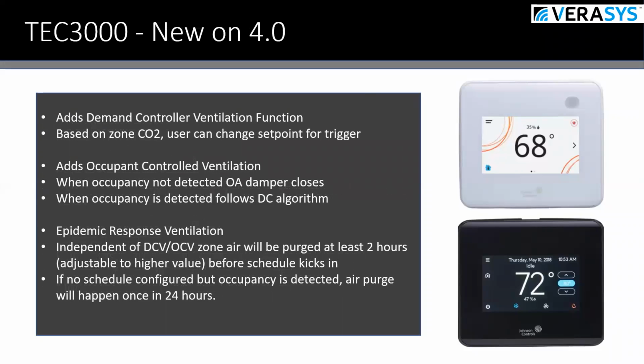What's new now on the TEC 3000s with the 4.0 update is that they're better suited than ever for these ASHRAE codes, because these mini controllers have built-in functionality to handle demand control ventilation based on CO2. They can trigger an air purge when occupancy is detected. It's really exciting that these TECs are so well suited for the building health market now.